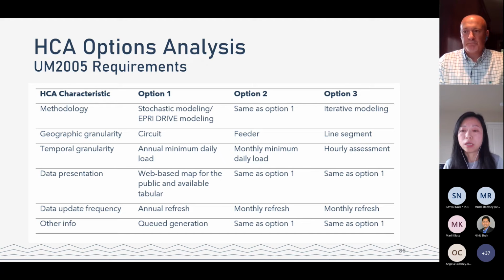Option 3 requires hourly assessment at the line segment. Performing hosting capacity analysis on an hourly basis at the line segment creates an exponential increase in the data collection needed, requiring expanded storage and processing capabilities and increased monitoring and data query processes. In many cases, new equipment will need to be deployed and existing equipment may need to be reconfigured. Next slide, please.